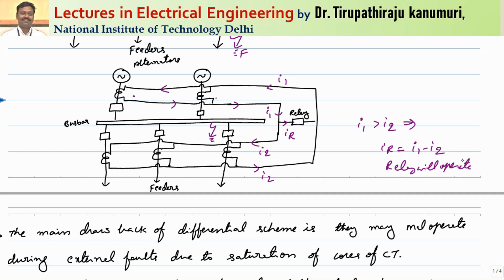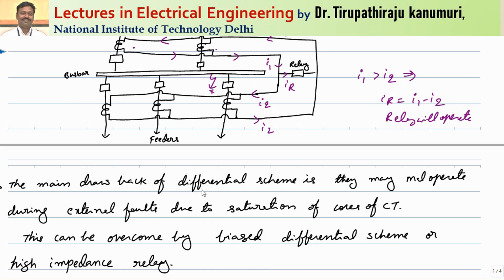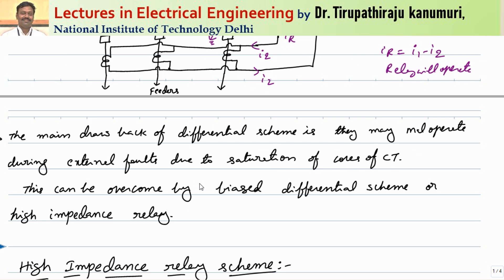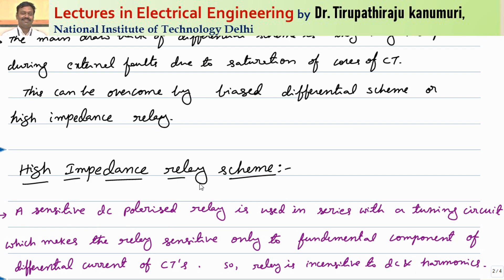Repeating once again: whenever the fault happens inside the protected zone — whether at your circuit breakers or on the busbar — the current entering will not be equal to current leaving. The difference in current will pass through your relay and your relay will operate. However, this has one major disadvantage: no two CTs will have the same characteristics. Because of that, some CTs may saturate earlier than the remaining CTs. So for external faults — also called through faults — different CTs will saturate at different points, causing different secondary currents, which leads to mal-operation of your relay. To overcome this, we use either a bias differential scheme or a high impedance relay.